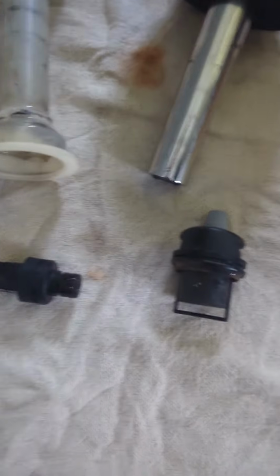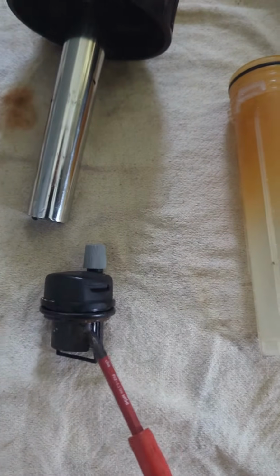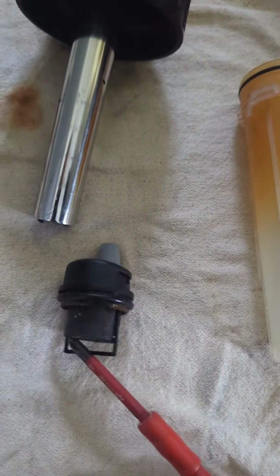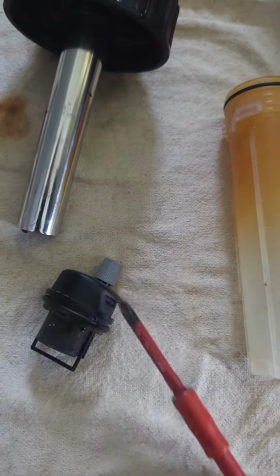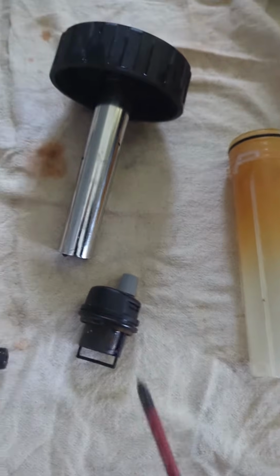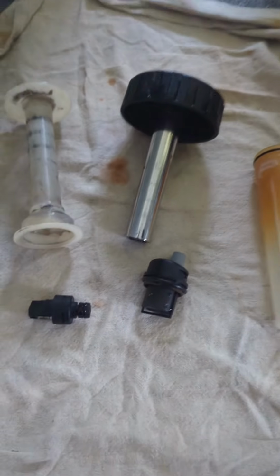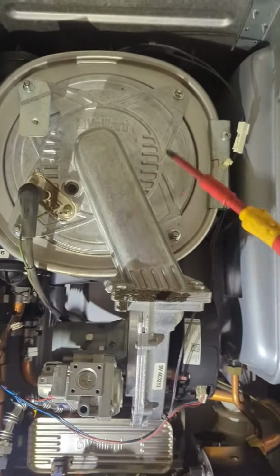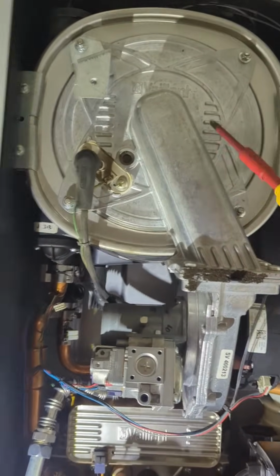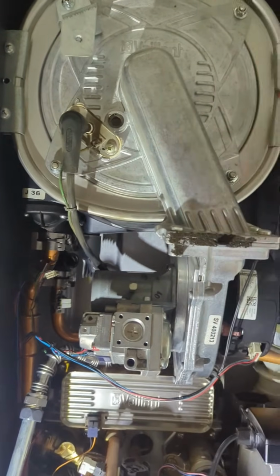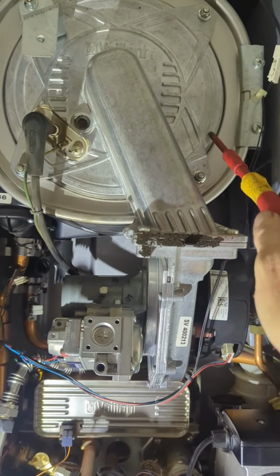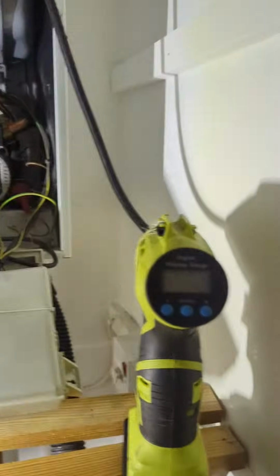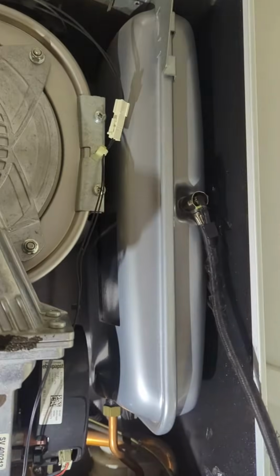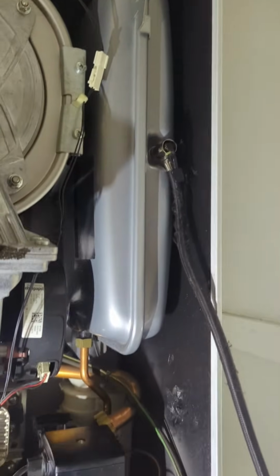Now, these are the parts clean. You can see the difference in the filter now. The automatic air vent was really dirty, and what will happen is this float won't rise up, and we'll have a leak inside the boiler. So it's important we clean this every year. Every five years, we'll need to go into the main heat exchanger so we can inspect and clean the electrodes, clean the main heat exchanger itself, and we'll also replace the seals and the nuts around. Draining the boiler and pumping up the vessel is important, as it'll prevent a loss of pressure.